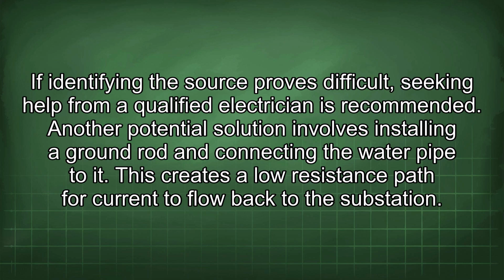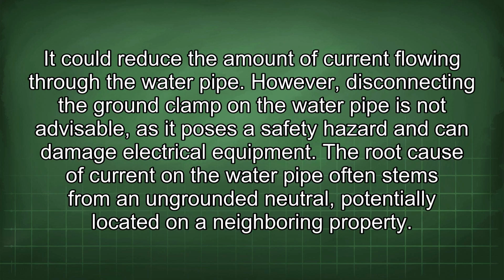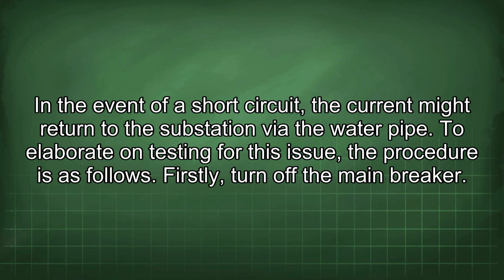Another potential solution involves installing a ground rod and connecting the water pipe to it. This creates a low resistance path for current to flow back to the substation. It could reduce the amount of current flowing through the water pipe. However, disconnecting the ground clamp on the water pipe is not advisable, as it poses a safety hazard and can damage electrical equipment. The root cause of current on the water pipe often stems from an ungrounded neutral, potentially located on a neighboring property. In the event of a short circuit, the current might return to the substation via the water pipe. To elaborate on testing for this issue, the procedure is as follows.